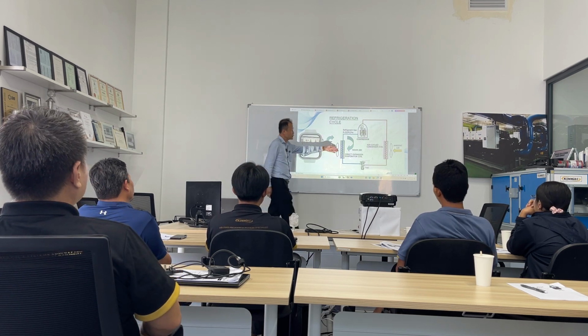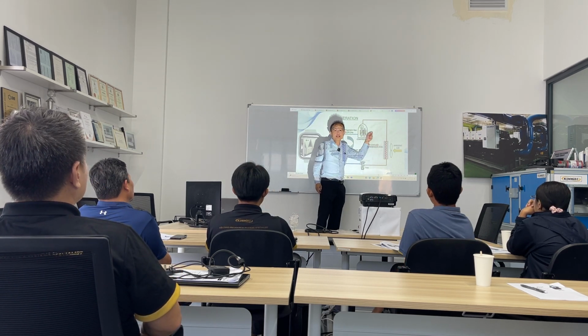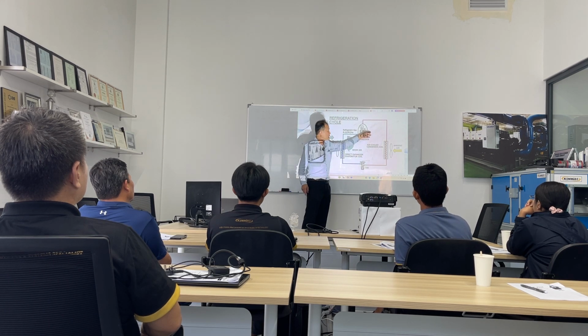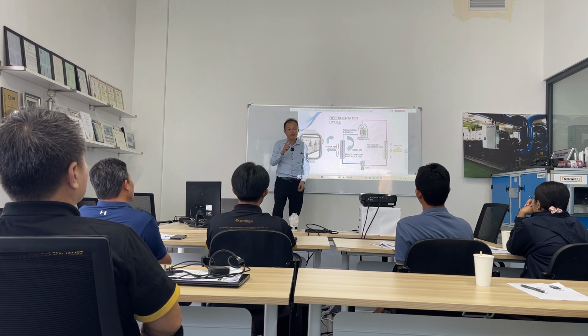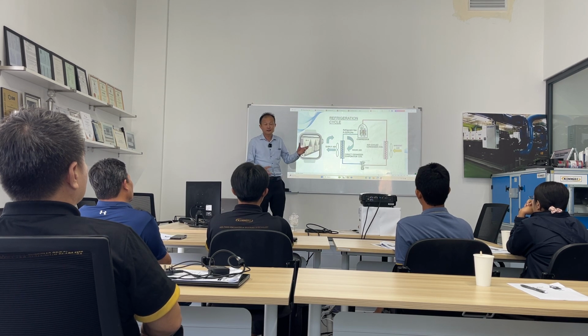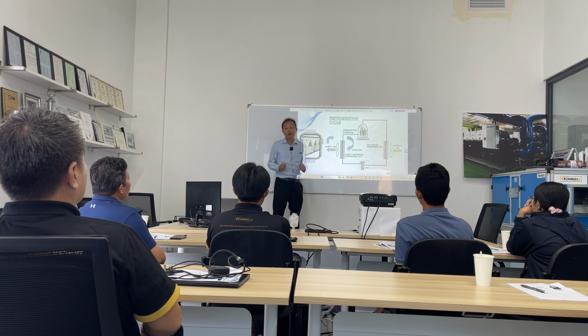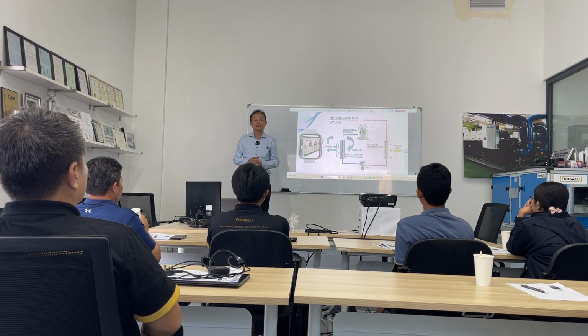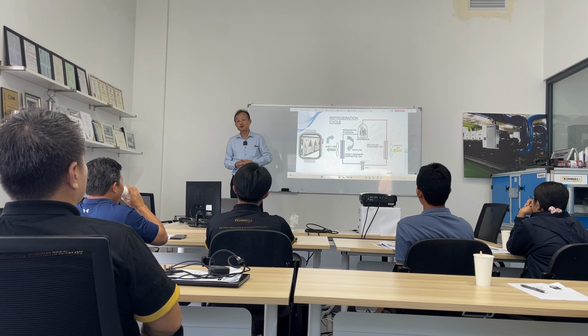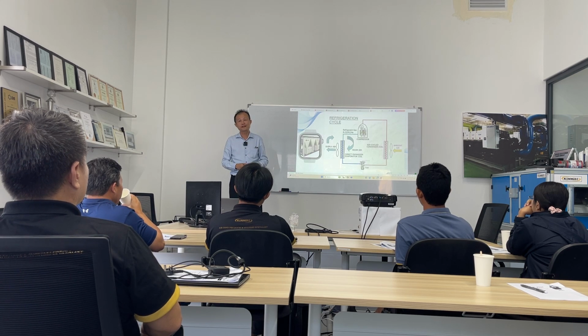You know, for air-cooled systems, for every 1 ton of cooling that you need to provide, it consumes 1.2 kilowatts or 1.4 kilowatts. It's very power consuming, you know. So of course that comes back to our operation here.